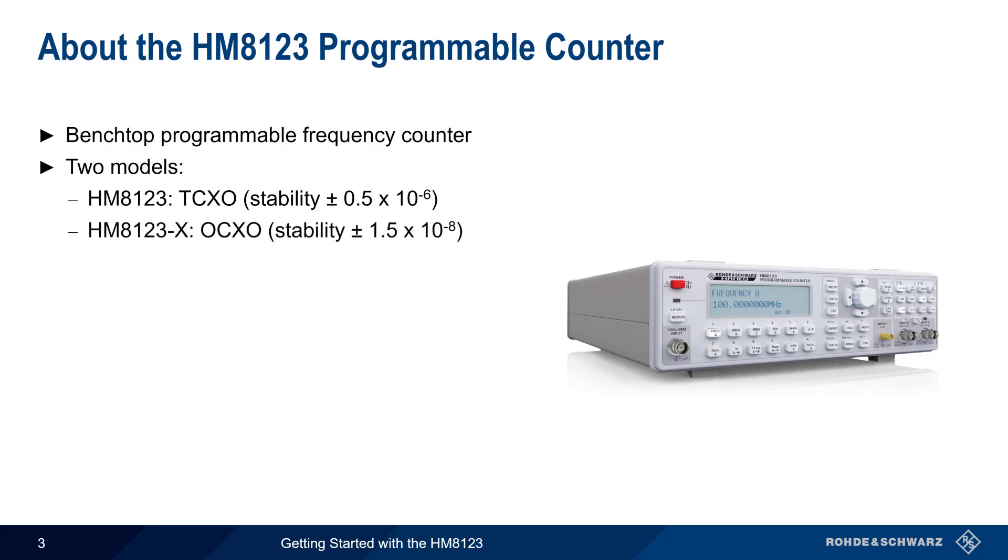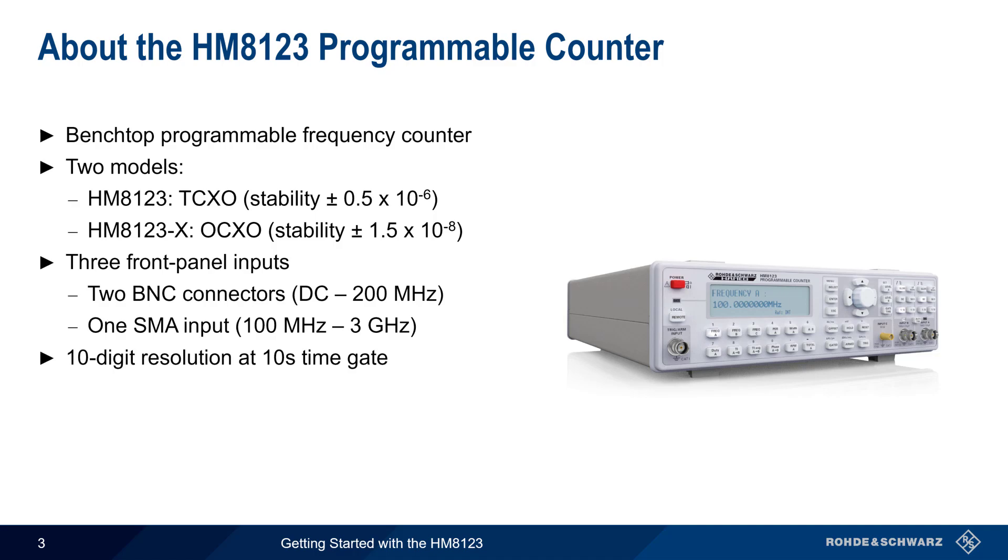The Rohde & Schwarz HM8123 is a benchtop programmable frequency counter that's available in two models. The standard HM8123 has a temperature-controlled oscillator, and the HM8123X has an oven-controlled oscillator for greater stability. Both models have three front panel inputs, two BNC connectors that can measure signals from DC to 200 MHz, and a single SMA input that covers the range of 100 MHz to 3 GHz. The HM8123 can provide up to 10 digits of resolution when the gate time is set to 10 seconds or longer.